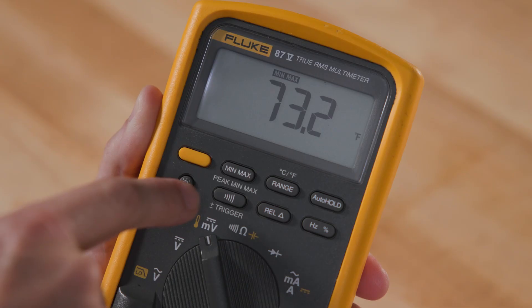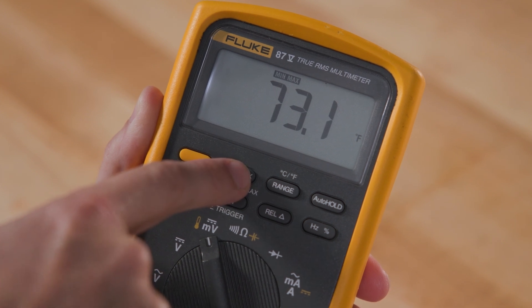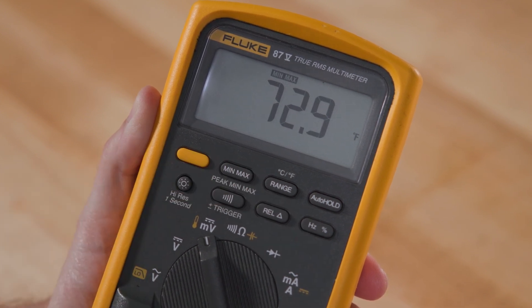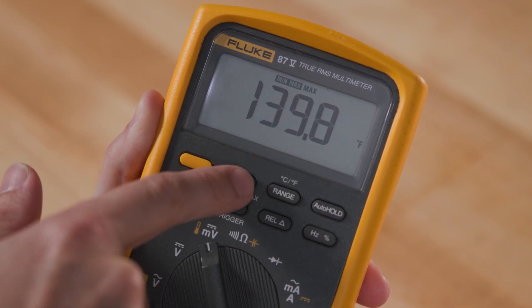Taking the measurements one step further, there are a couple of modes that come in handy when looking at temperature: Min-Max mode and Relative mode. Min-Max mode is especially useful for temperature measurements — it allows the multimeter to record the minimum and maximum readings over a period of time. To use this mode, simply press the Min-Max button after starting your measurement. The 87V will save the information and display the highest and lowest readings it registers.